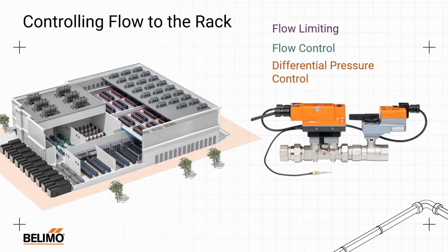This is a whole different way of thinking about it. So when we do differential pressure control, and within the Belimo universe, that would utilize the Belimo energy valve and a differential pressure sensor. But the concept of controlling to a fixed differential pressure can be done in many different ways. So we don't own the rights on the ability to control to a differential pressure. We just have a solution that fits into that space. But let's talk about why you would want to control to a differential pressure.